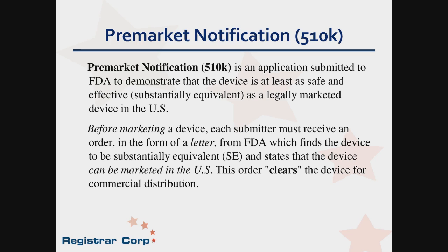So what is a 510K? The 510K is a pre-market notification, which is an application to the FDA to demonstrate that your device is as safe and effective, or the term that FDA is using, substantially equivalent to an already legally marketed device here in the US. So you would pick a competitor device that you know very well, and based on the data, you would show FDA that your device is as good, or maybe better, than the device that is already on the market. When FDA has reviewed the data that you send in, FDA will send you a letter that clears your device. After you have that letter from the FDA, you can start selling your device here in the US. Not before. You really have to wait till that clearance letter is in your mail at the end.